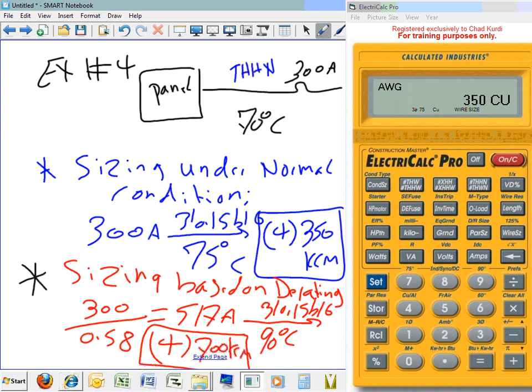Done. Ask yourself, is the size that I came up with more than 350? Yes, we're okay. If you came up with 250 here, you cannot size a conductor less than what the normal condition is. Very, very important. So for most applications, that step in blue that I told you about is really worthless for all practical reasons. But there are circumstances, and I've seen it done, where you can do the derate and you end up with a conductor higher than what you should have used to start with.